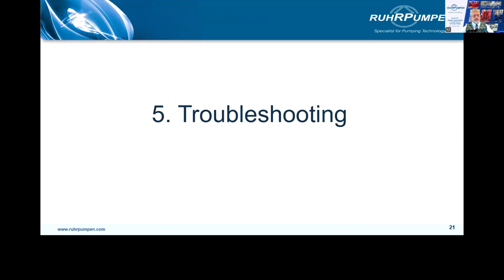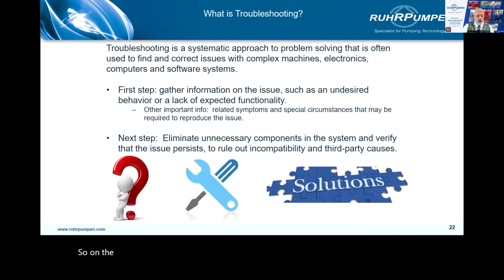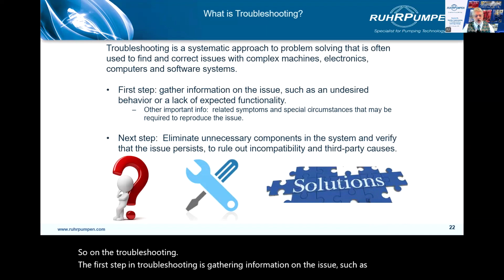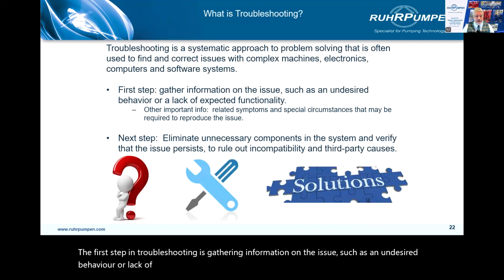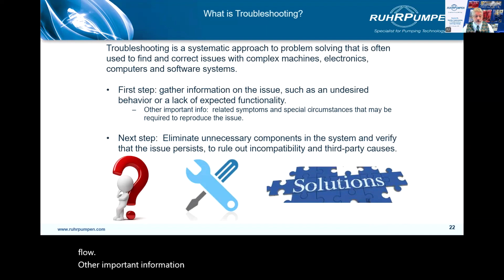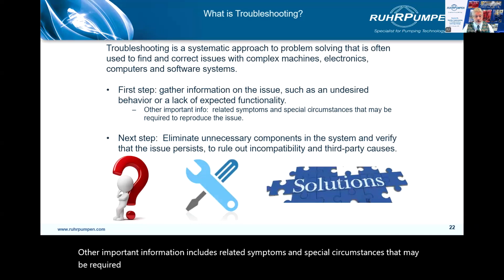So on to troubleshooting. The first step in troubleshooting is gathering information on the issue, such as an undesired behavior or lack of expected functionality, maybe noise, maybe vibration, maybe lack of flow. Other important information includes related symptoms and special circumstances that may be required to reproduce the issue. For example, if it's a vibration issue, maybe it only occurs at higher flows, or lower flows.